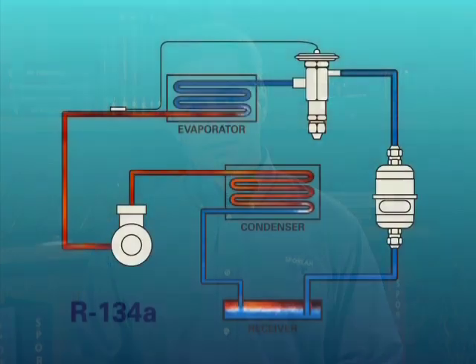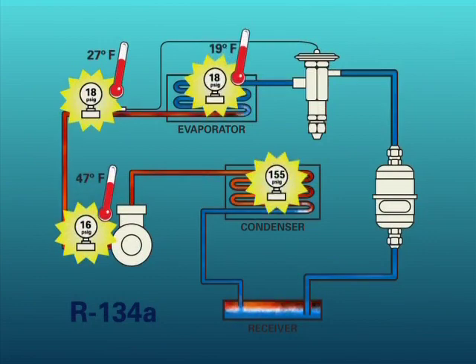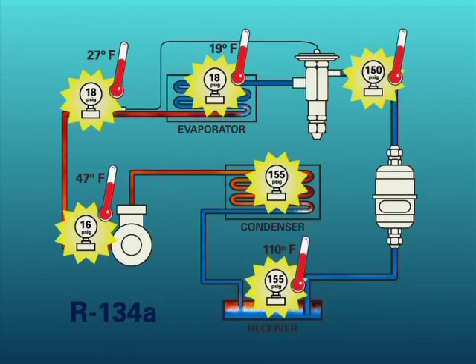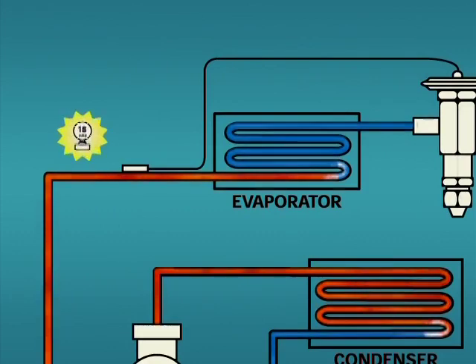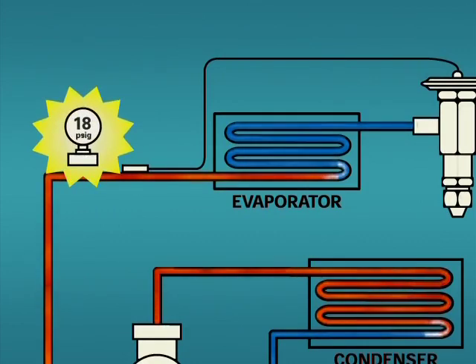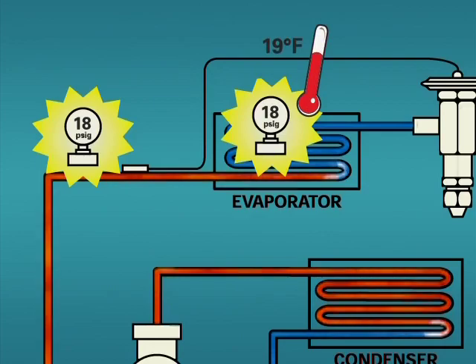Now that we understand the basic principles of the PT relationship, let's start to analyze a system for superheated, subcooled and saturated conditions. This system diagram shows some actual pressure temperature measurements of a normally operating system using refrigerant 134A. The measured pressure at the evaporator coil outlet is 18 PSIG. Assuming there is minimal pressure drop in the evaporator coil, we will have an 18 PSIG pressure in the coil. 18 PSIG on the PT card indicates a temperature of 19 degrees Fahrenheit.